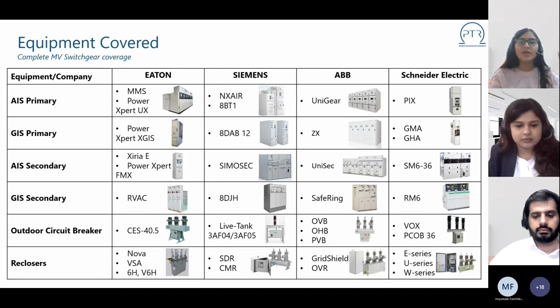medium voltage switchgear equipment available in the market. All tier one players, Eaton, Siemens, ABB, or Schneider cover the market from different perspectives depending on the distribution level, like primary switchgear employed in HV to MV primary distribution, and secondary switchgear employed in secondary distribution. Depending on the insulation, it is categorized into AIS and GIS.